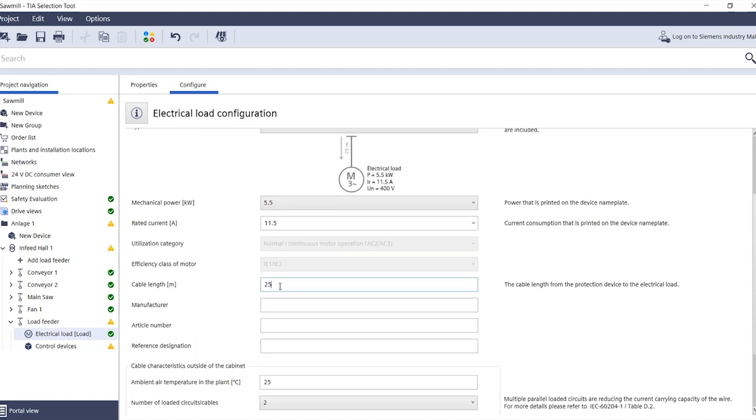You can then enter the cable length. This is essential for the short circuit current because it significantly dampens the current by adding resistance. Here you should specify the cable length from the protection device of your load feeder to the load.